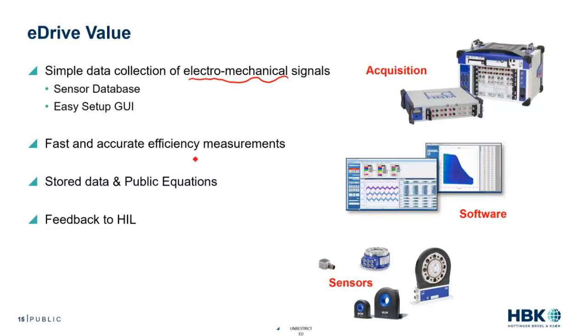Within this idea of electromechanical signals, we have a sensor database where we can set up the scaling of a sensor — whether a simulated sensor, where the Opal RT gives a scaled value like 0 to 10 volts representing 0 to 100 newton meters, or a real torque sensor with a frequency output representing the same value. This database lets us acquire real and simulated sensors and access them in our software for easy switching from simulation to real hardware.